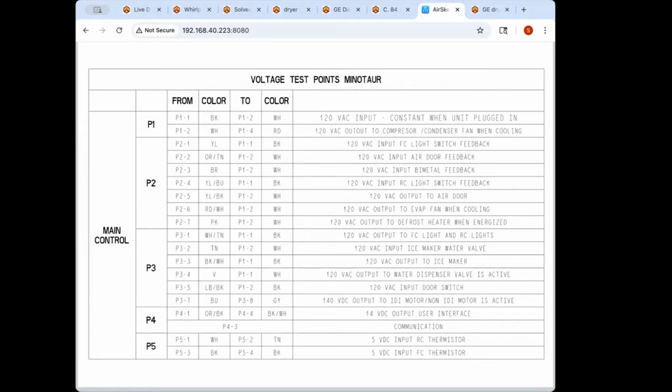If it's working in spec, then in one position, fully open, you should have either 120 or 0. They don't say which one. And then in the other state, you should have the opposite. If you're watching the damper move, I mean, it's just a little stepper motor or synchro motor, I think, and so they move slow. But if you're watching the damper open and close, that is the frequency. You can visually tell it.